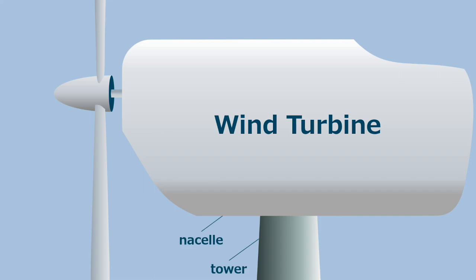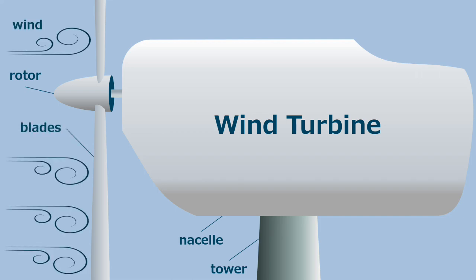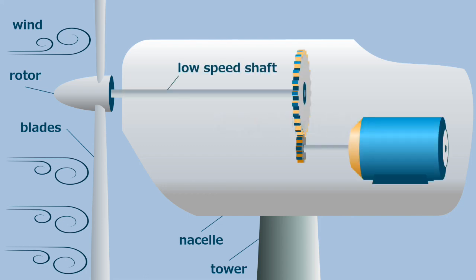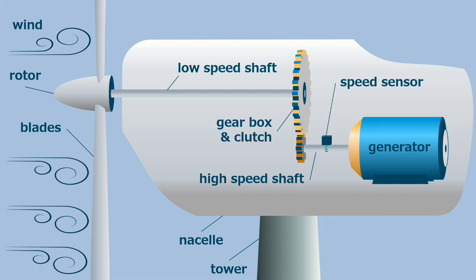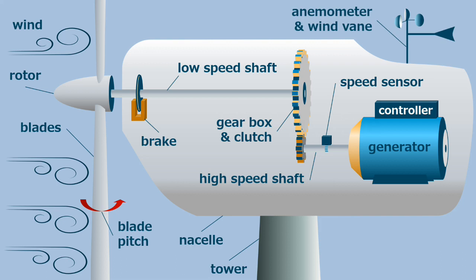So, we have the nacelle and the tower, the rotor, and the wind that impulsionates the blades. This makes the low speed shaft rotates, and through a gearbox and clutch, to make the high speed shaft rotates, that is connected with the generator. We have a speed sensor, that provides a signal to a controller, and we actuate on the blade pitch, changing the amount of wind power that goes within the turbine. Additionally, we have a brake system, and some anemometer and wind vane, to control the yaw drive, so we can align with the wind direction.